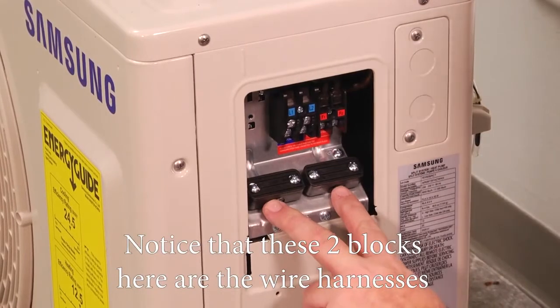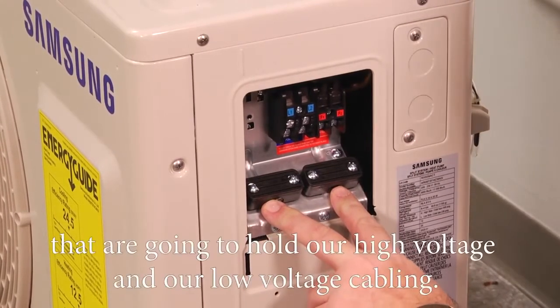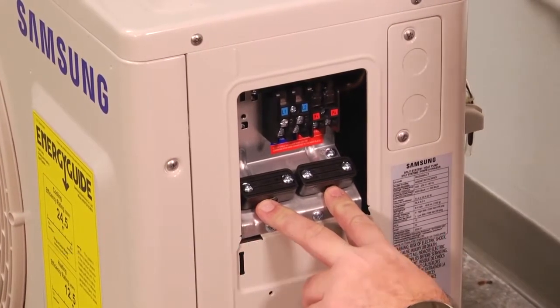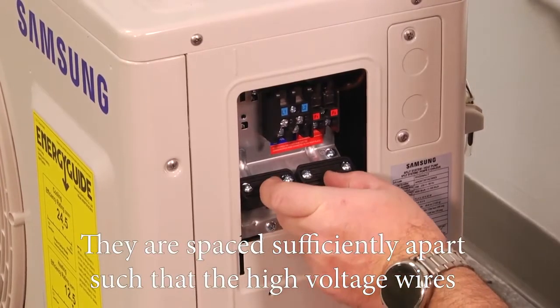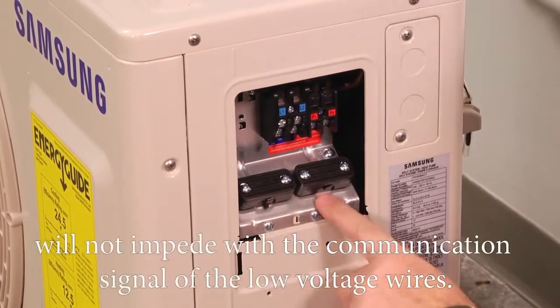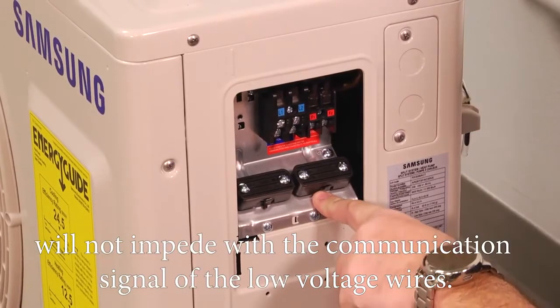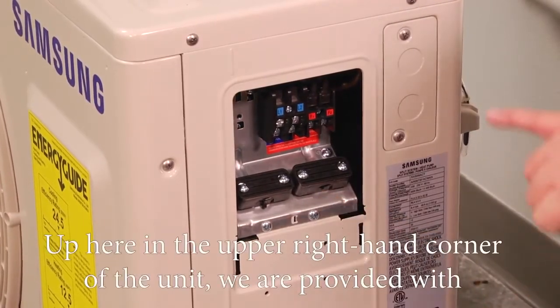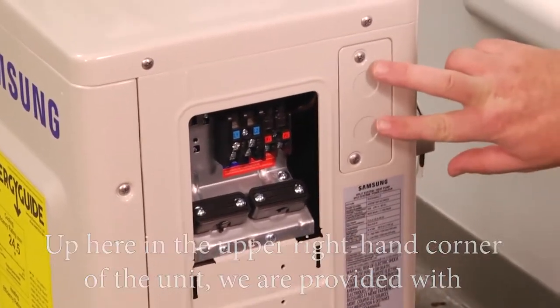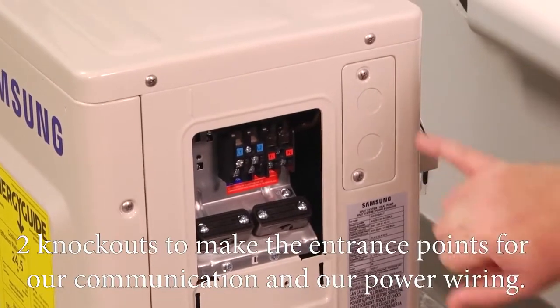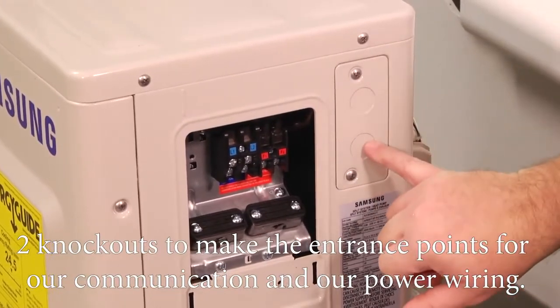Notice these 2 blocks here are the wire harnesses that are going to hold our high voltage and our low voltage cabling. They're spaced sufficiently apart so that the high voltage wires will not impede with the communication signal of the low voltage wires. And up here in the upper right hand corner of the unit, we're provided with 2 knockouts to make the entrance points for our communication and our power wiring.